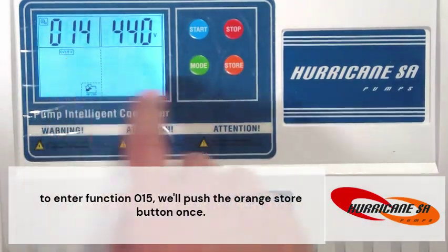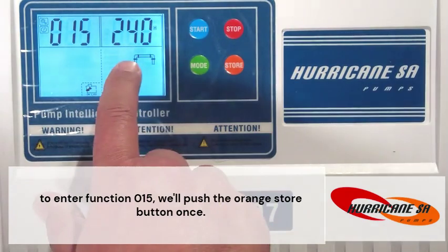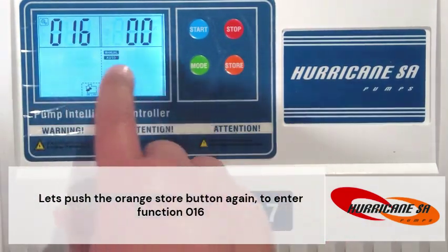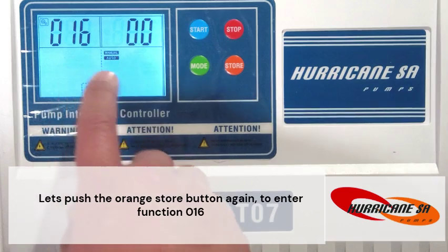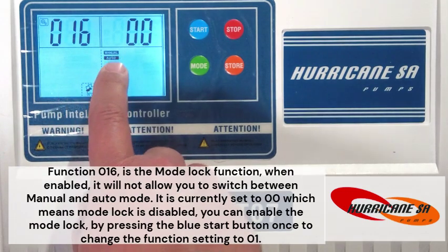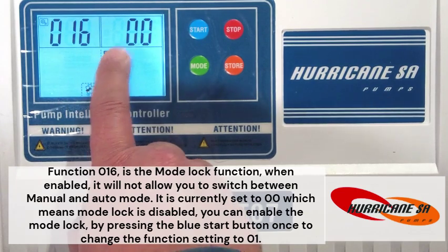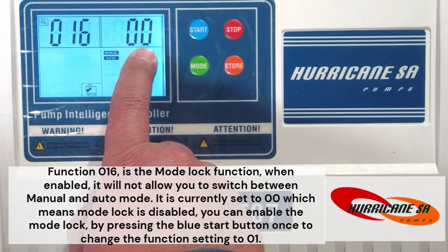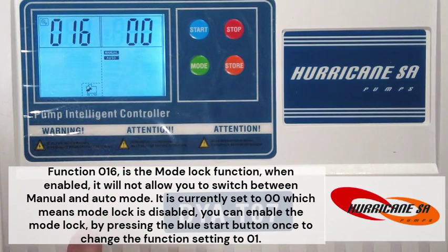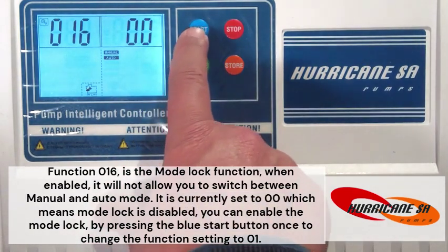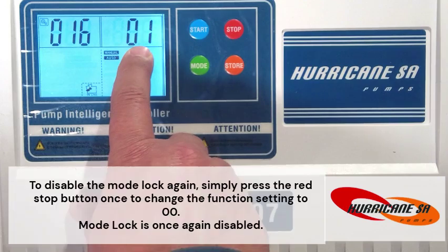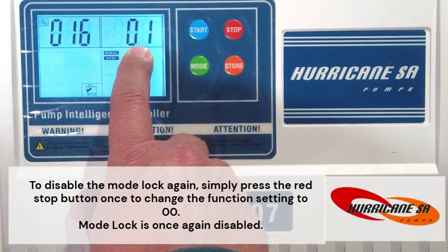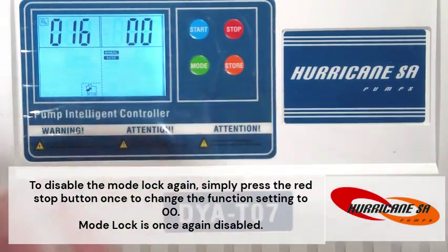To enter function 015, we'll push the orange store button once. Let's push the orange store button again to enter function 016. Function 016 is the mode lock function. When enabled, it will not allow you to switch between manual and auto mode. It is currently set to 00, which means mode lock is disabled. You can enable the mode lock by pressing the blue start button once to change the function setting to 01. To disable the mode lock again, simply press the red stop button once to change the function setting to 00. Mode lock is once again disabled.